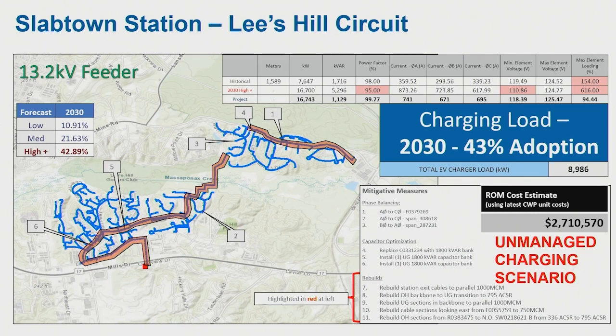It's not even close. And in fact, the remediation for that is so substantial, it involves different operating voltages. For any of you in the operations side, that means everything changes: all the cable, all the transformers, everything. If you have to up the voltage, a different class of voltage for your underground systems, much bigger conductor requiring much bigger conduit that we didn't put in the ground, bigger conductor on the overhead grid which we didn't plan for back in the day. We could easily be upside down on transformer loading.